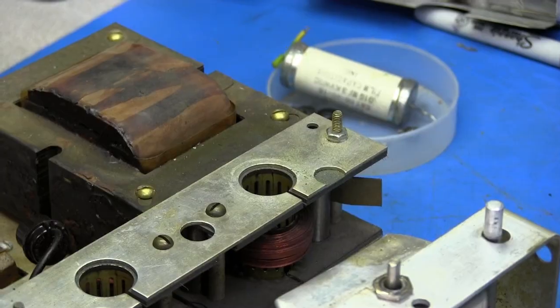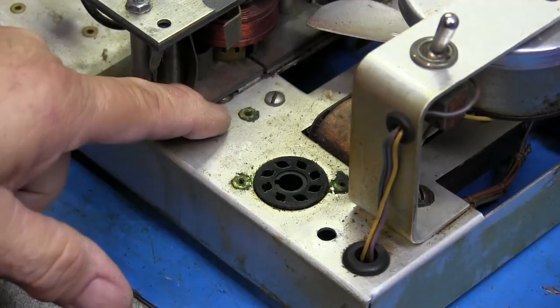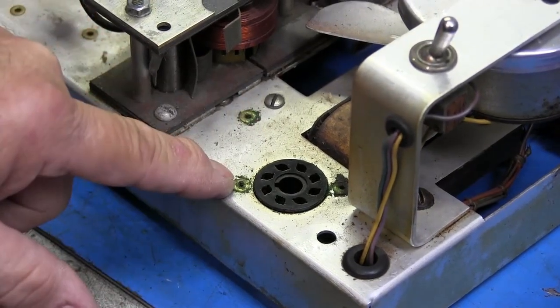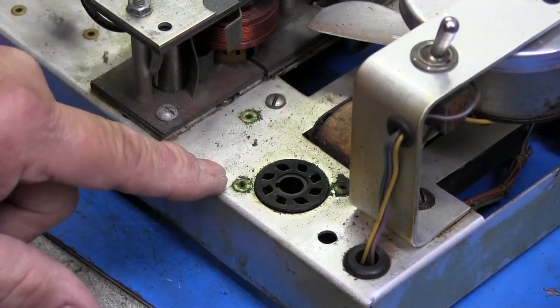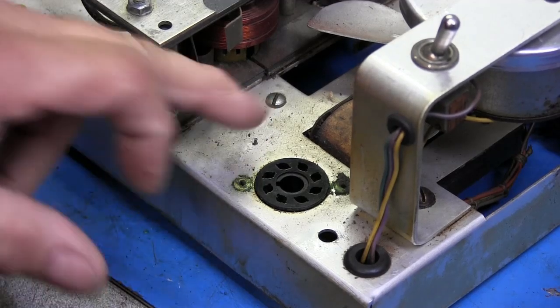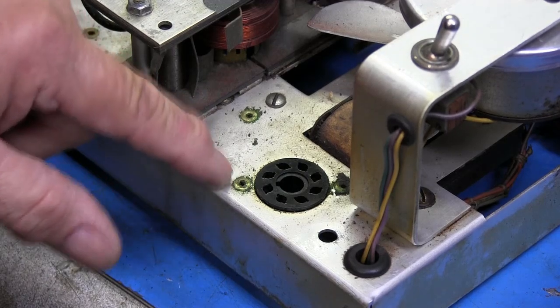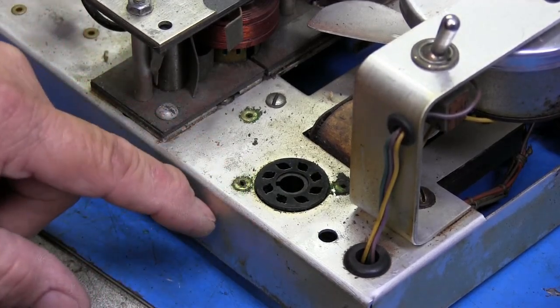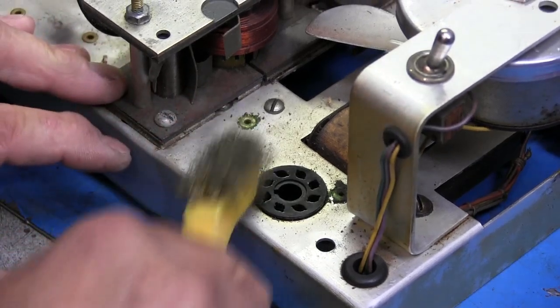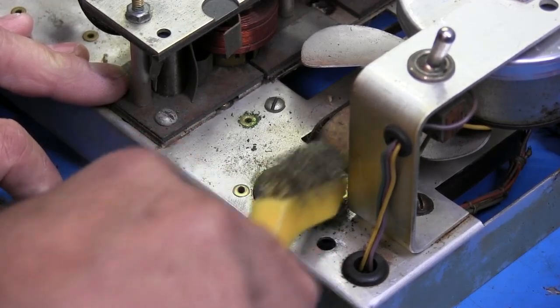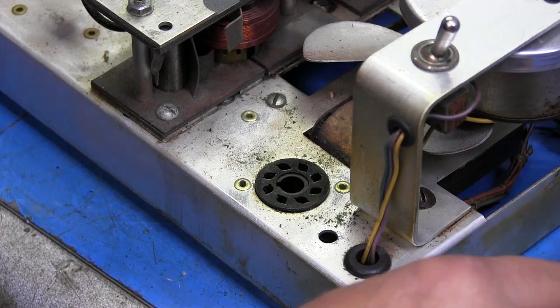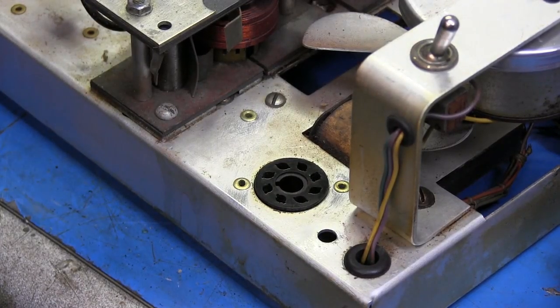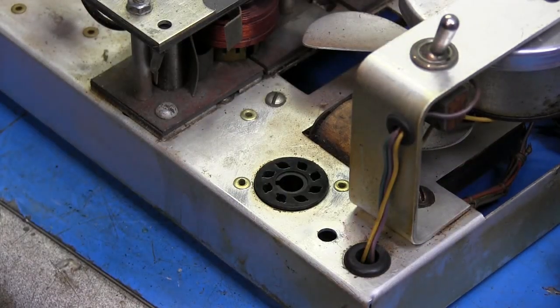You see some around some of the rivets here on the bottom. It's still got that green corrosion, so if these are ground lugs, they're not going to make very good connections. So we'll have to look at that underneath and see if they're actually using for grounding, because I'm pretty sure that corrosion is seeped all the way around this rivet, and you know that's going to keep the rivet from grounding to the chassis. Or it's the outer part of it, it just scrubs right off, so no problem at all. So I'm going to go and get this thing cleaned up. I'm not going to bore you with showing the cleaning process, so I can get the chassis back looking halfway decent.